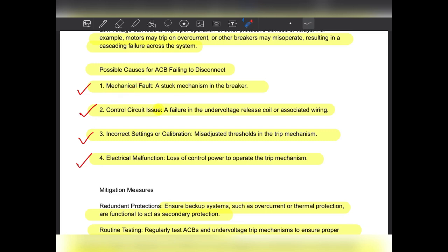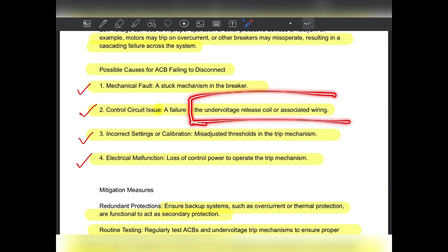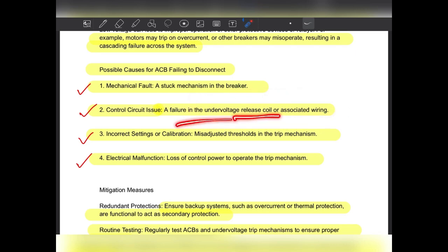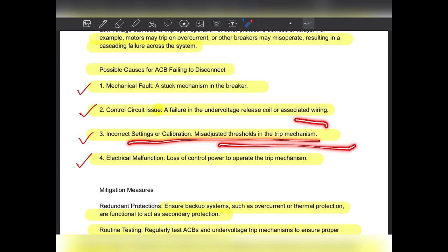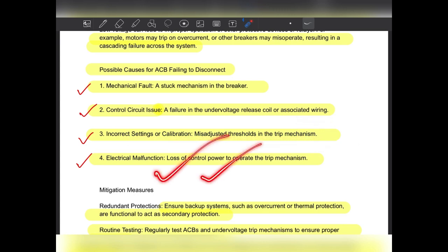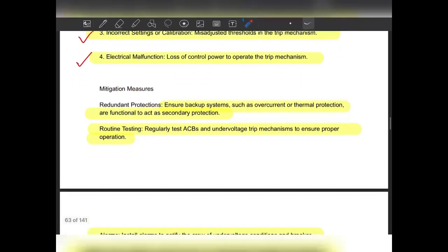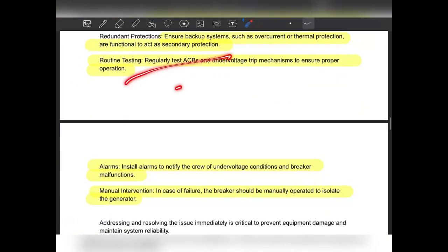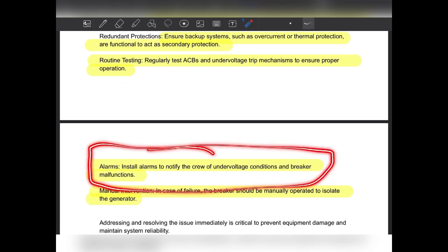There may be a mechanical fault, maybe some mechanism is stuck inside the breaker. We have to isolate the breaker, rack out the breaker, and check everything. Then a control circuit issue, maybe the under voltage relay is not working and will not trip the circuit, because there is a loss of power in the under voltage circuit, a control power failure. Then an incorrect setting in the under voltage relay, so it will not trip the breaker. And an electrical loose connection, a control power loose connection may also be there. So we have to check everything one by one. And first, to troubleshoot, we have to check which alarm came just before the breaker tripped, and according to that we have to troubleshoot.